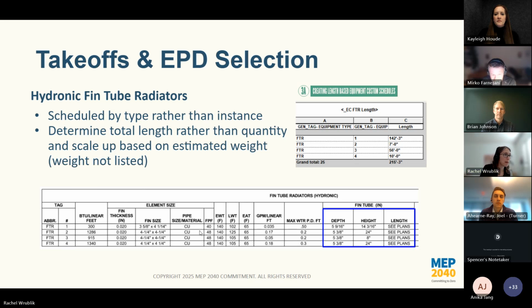So what we ended up doing is creating a length-based custom schedule to figure out what the length is of each type. You can see it here, FTR1, there's 142 feet of it, and so on and so forth. And then from there, we looked at estimating the weight for each of those types. You can see on the schedule that each one is slightly different. So we didn't want to just add up the total linear foot. I guess you could roughly estimate that, but ideally you're assigning a weight to FTR 1, 2, 3, and 4, and then scaling there.